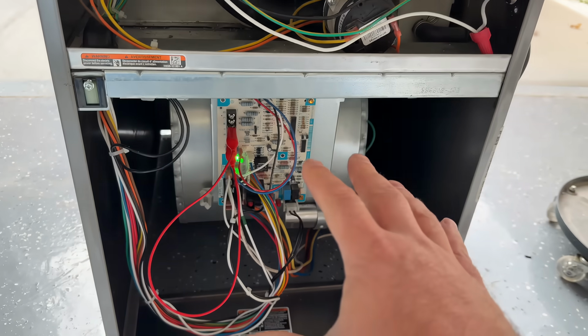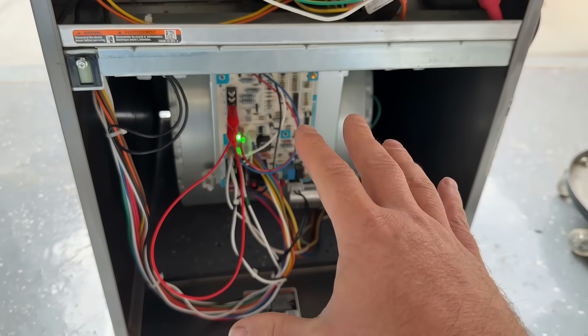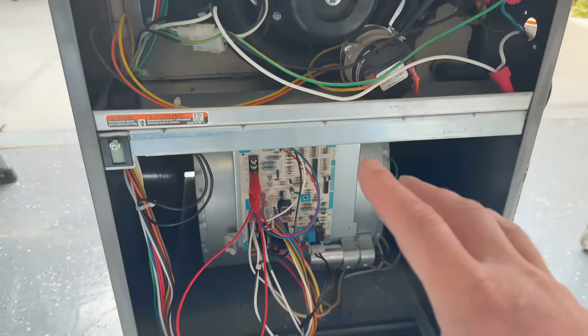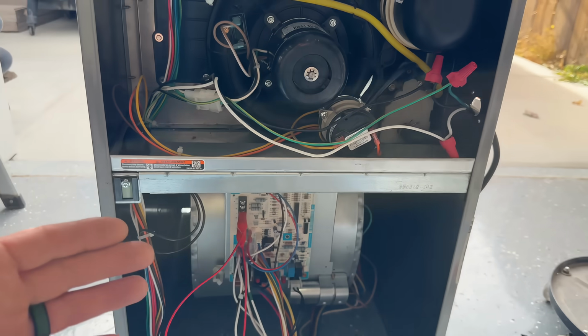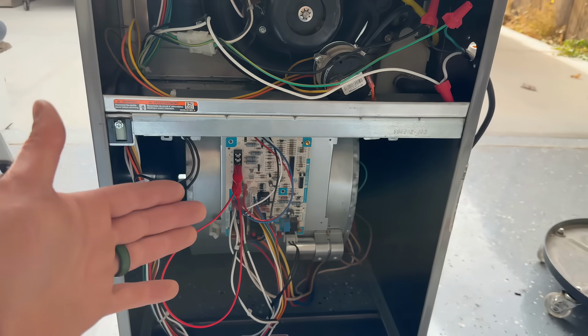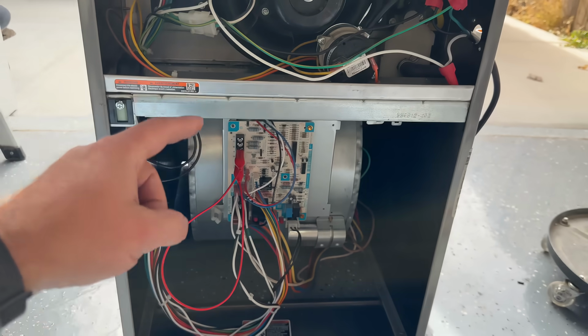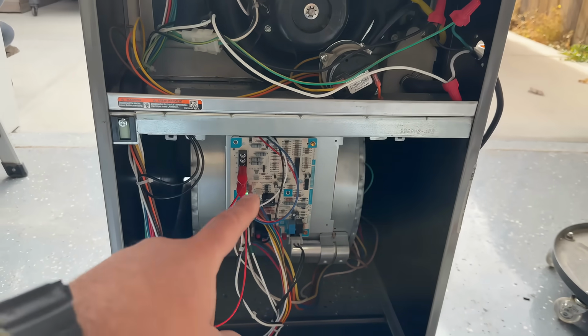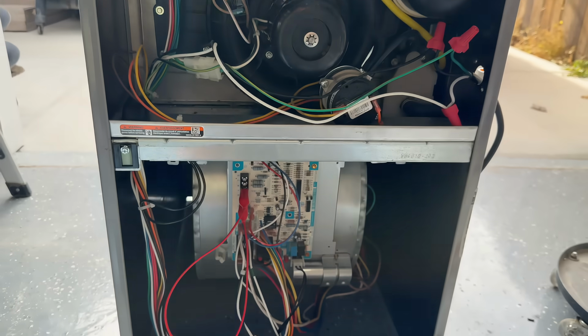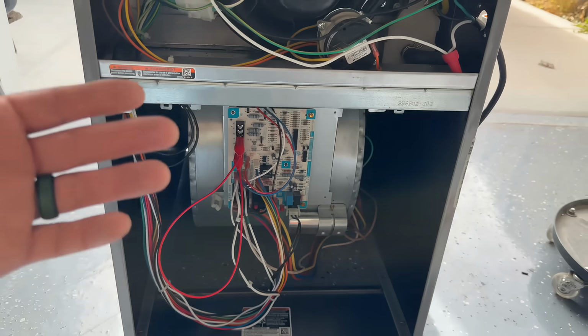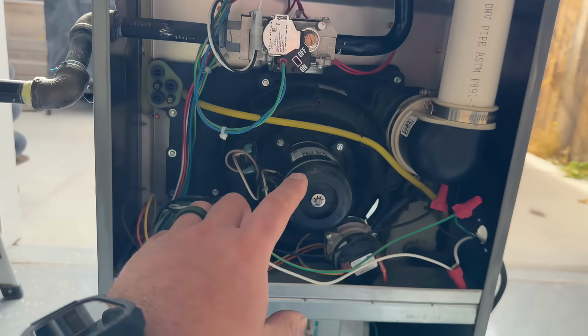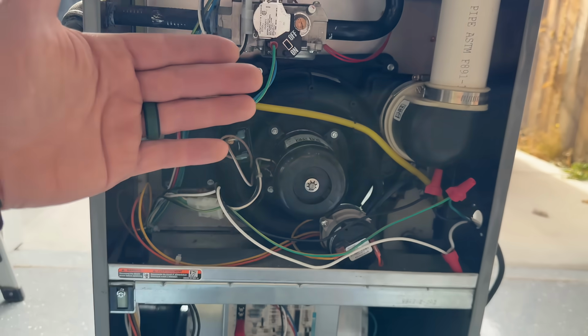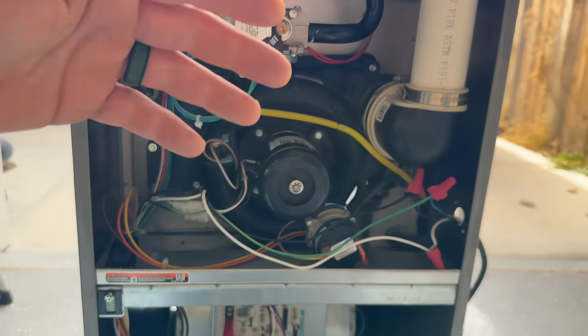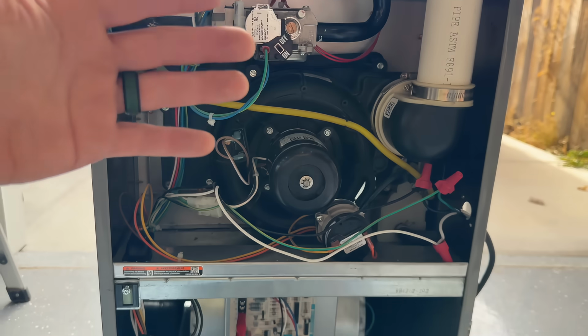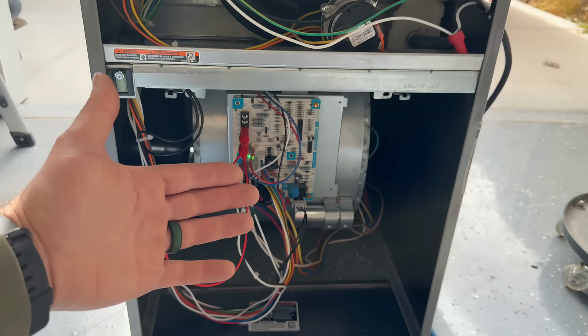Okay, so our blower motor is going to come on first and run for about 60 seconds, and then the inducer will come on. Some furnaces don't have this feature, but this furnace does, like a self-test to make sure that the blower motor is working before any of the combustion stuff turns on, which is pretty nice. But a lot of times you don't have this. The gas portion will immediately start, the inducer will start, and then once everything is fired up, after about 30 seconds, our blower will turn on.